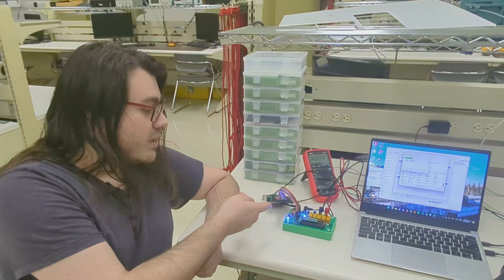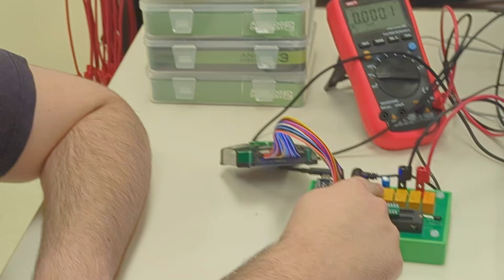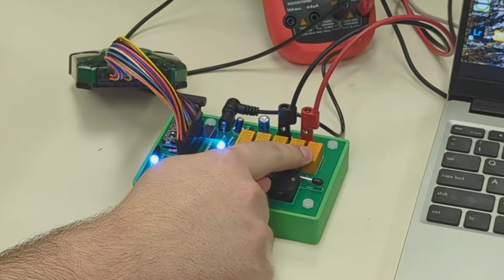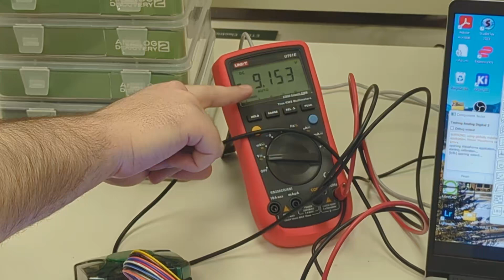So, we designed our custom semi-automated component board to help automate the calibration process. We have these relays, which configure the different wiring states that are necessary to calibrate the AD2, which is plugged into this nice zero insertion force socket, which allows for many insertions. This microcontroller is connected via USB-C to the computer, and the computer sends commands through the firmware to control the relay states. And the digital multimeter is plugged into the board on this calibration bus to measure the different voltages that are needed for the calibration.